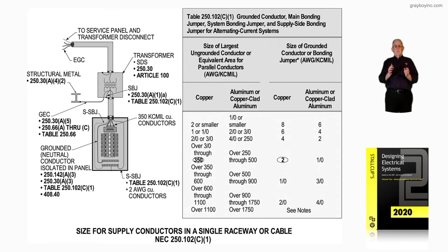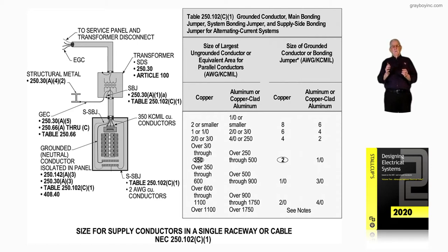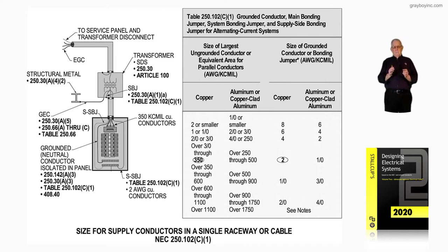The table drops down below that header information and talks about, to the left, the size of the largest ungrounded conductor or equivalent area for parallel conductors, giving you the AWG or KCMIL rating. To the right, it talks about the size of the grounded conductor or bonding jumper, again giving you the AWG size along with the KCMIL rating. That grounding or bonding jumper conductor is sized to provide an effective ground fault path to transfer fault currents when they occur.